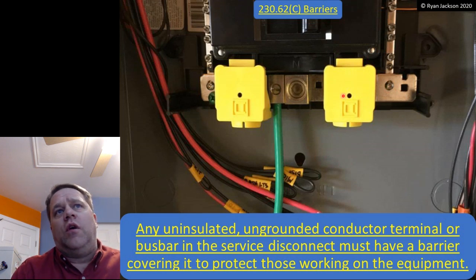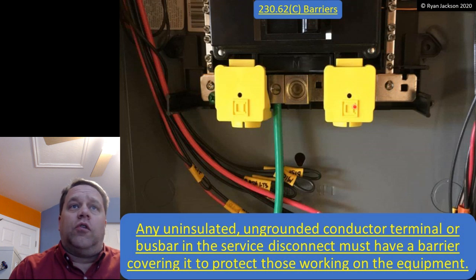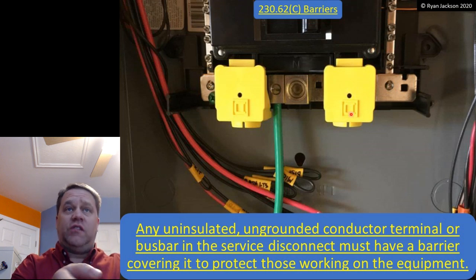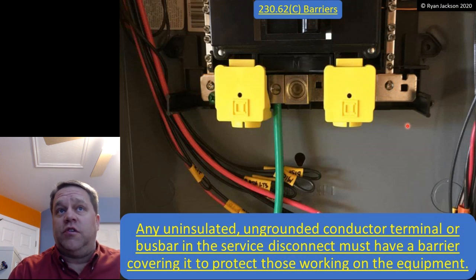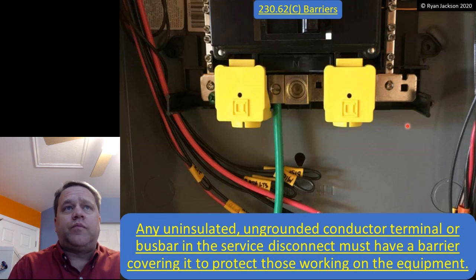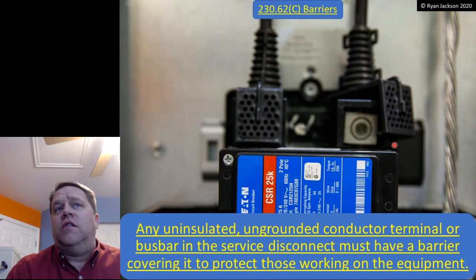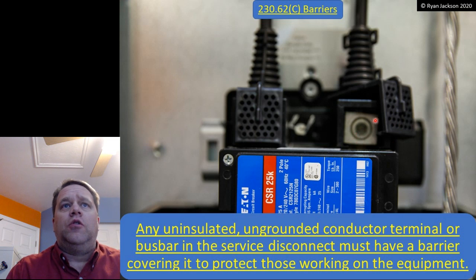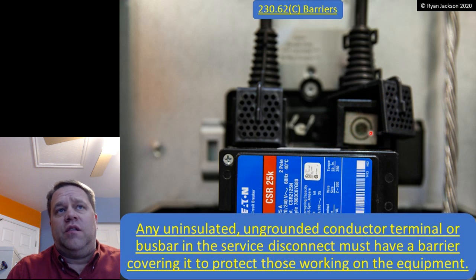This is obviously Square D's solution. These little holes right in the middle allow you to put your test leads in so that you can test it for voltage or the lack thereof. This one is Eaton Cutler Hammer, similar approach. So barriers, covers, something that covers the terminals that the service conductors land in.